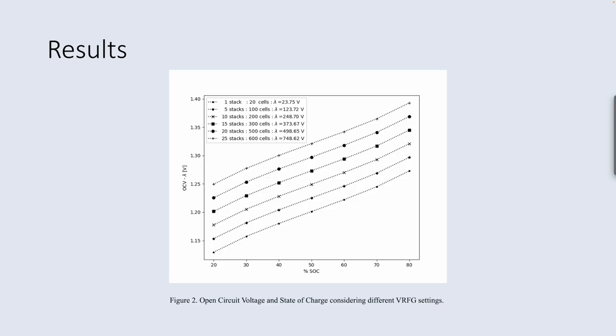In the results section, the state of charge can be determined using the mathematical equation described in previous sections, as shown in Figure 2, by knowing the open circuit voltage of the vanadium redox flow battery and the stack configuration. The open circuit voltage state of charge curves in Figure 2 are based on different stack configurations, and the axes represent open circuit voltage minus lambda, where lambda is a representative value selected based on the stack configuration. The addition of cells in the stack increases the potential and raises the open circuit voltage values. The state of charge is calculated between 20% and 80%, since this is the recommended range to avoid capacity loss. Figure 2 is a dynamic graph that can be used to understand the relationship and calculate the state of charge.